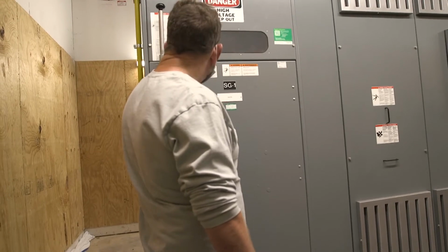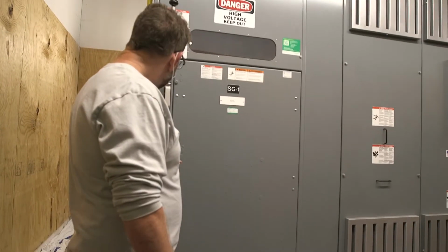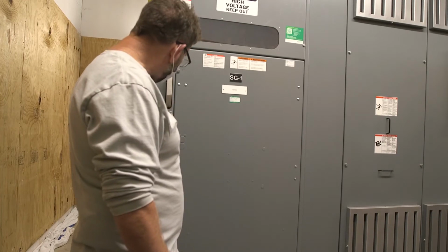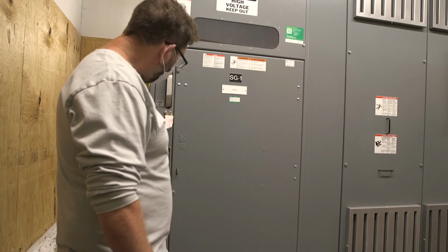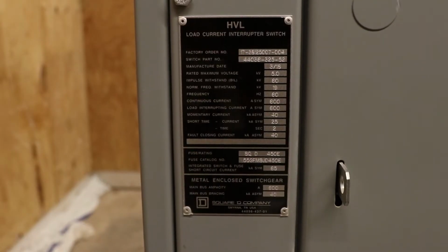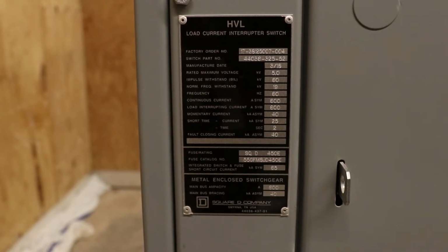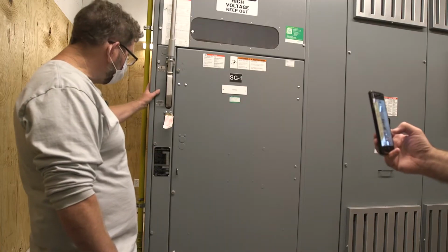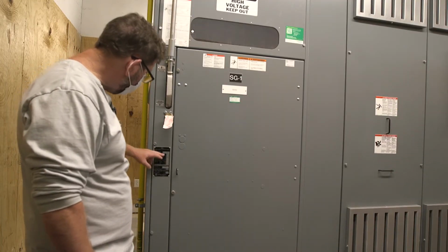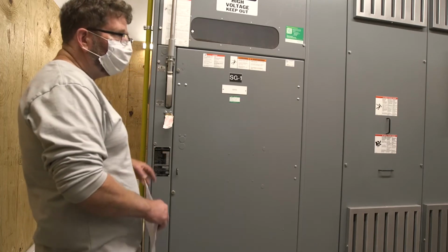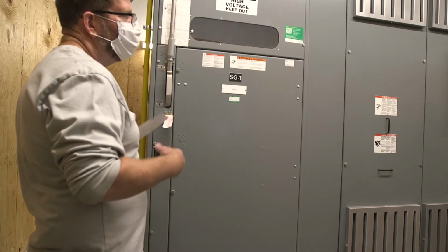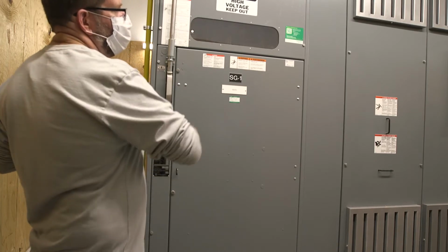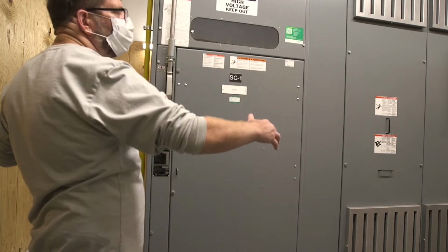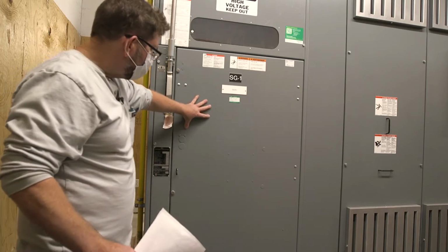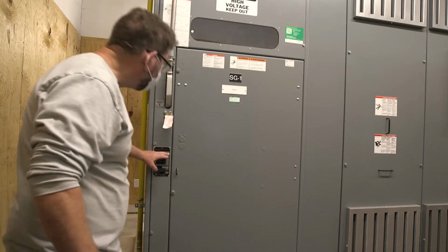This is our HVL, we call it an HVL. It's a medium voltage, enclosed medium voltage switch. One thing you'll find on all of our equipment, we have a factory order number. It's going to be on the nameplate of all the equipment. The first 2 digits are a code for the factory that made it. This was made in Smyrna, Tennessee, right outside Nashville. The next 8-digit number we call either a factory order number or a quote to cash number. It's a number that is associated with all the switchgear on this order. And then specifically this piece of equipment is the next 3-digit number, 001.